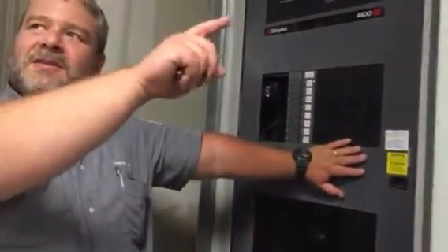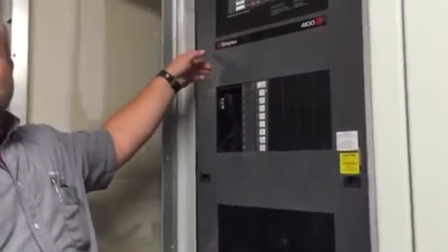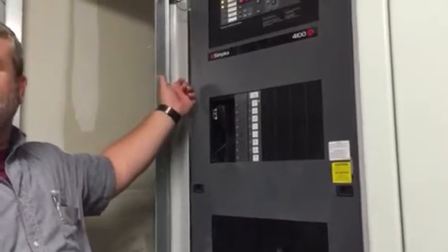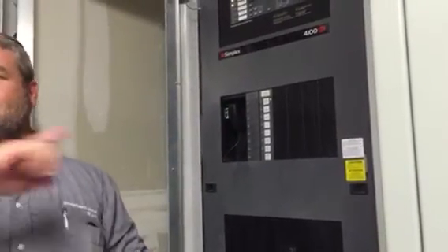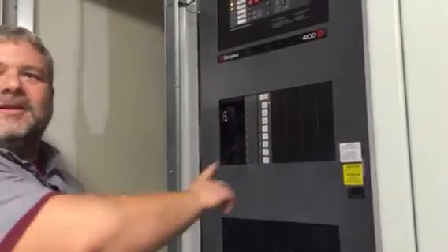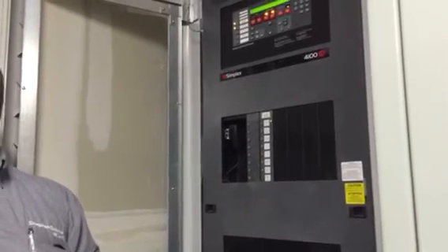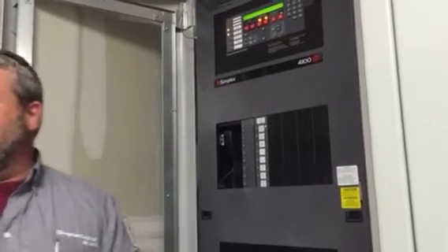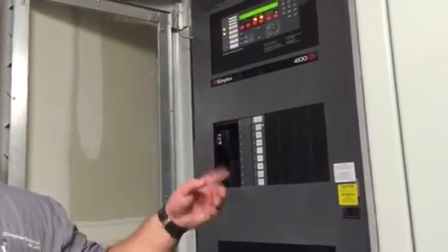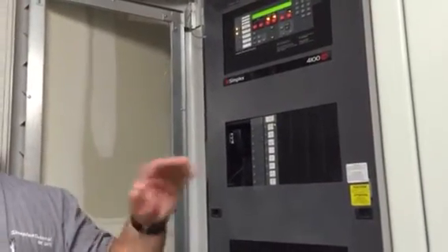You've got the two annunciators, one by the office, one by the gym entrance. In the elementary side, in the mechanical room back there, there's a beige box, a Simplex box. That's what we call a 4009 NAC extender that runs strobes for the elementary. And then there's another one over here in the multi-purpose building, by the girls' locker room, that little janitor's office. So there's those two sub panels. Those two sub panels run strobes. They don't do anything else other than that.